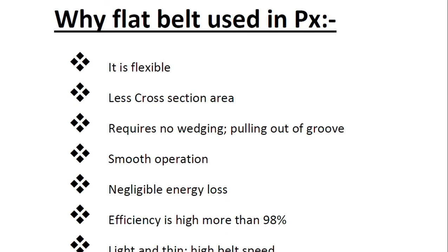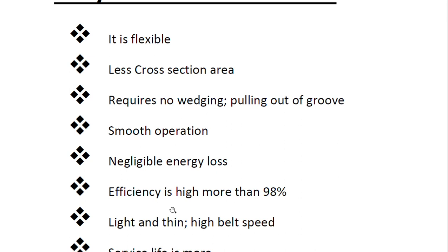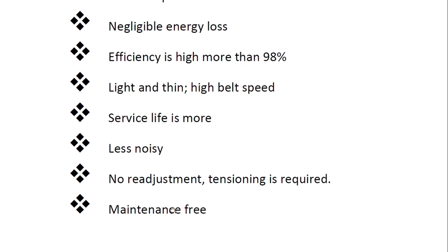There is negligible energy loss with a flat belt — efficiency is high, more than 98%. It is light and thin, because of which it supports very high speed. The purifier has a very high speed of rotation, so this is an important point. Service life is more because of less maintenance and higher efficiency. The flat belt is also less noisy, as there is no wedge and less cross-section area, so the noise produced is very low.